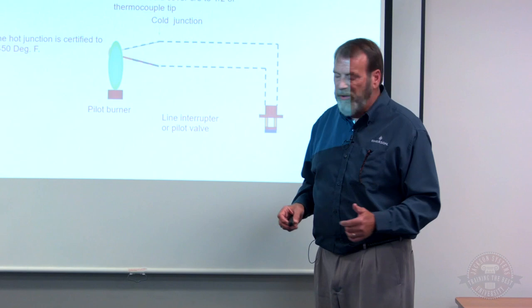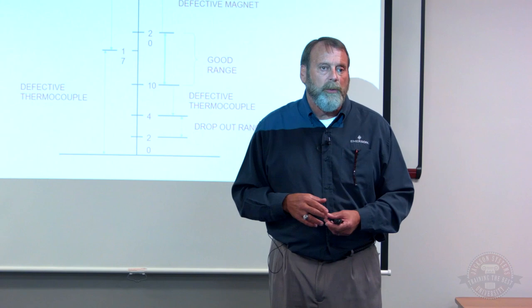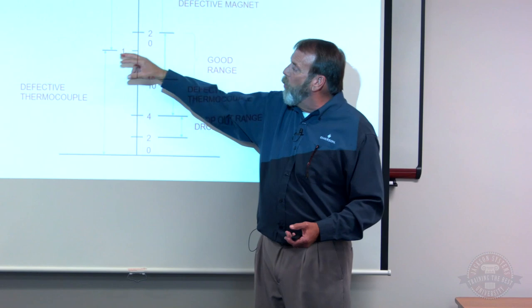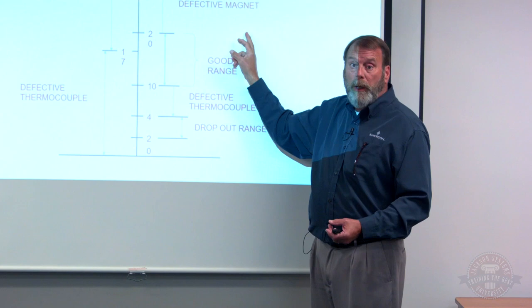If you want this, we can send it to you. This is just a nice little check. If you're ever doing any water heating work, or if you have any plumbers or HVAC guys doing service work on standing pilots, you can check how many millivolts a standing pilot is putting out in what they call an open circuit, which is where you pull the thermocouple off, and you have just that little button down at the end. You can check it as no load, or you can check it closed, closed meaning it's attached to the gas valve.